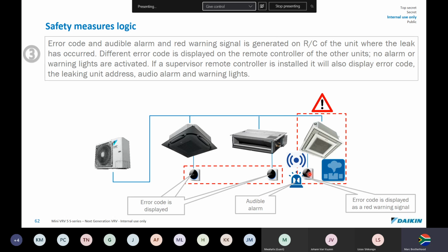So it'll happen on this remote. Different error codes are displayed on the remote controller than that of the other units. So these units might say A1, this one might say C6, because this is the faulty unit, okay? Excuse me. No alarm or warning lights are activated in these rooms, okay? The alarm's only going to go off in the room where there's a leak.